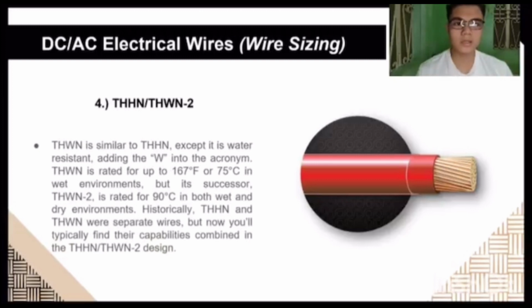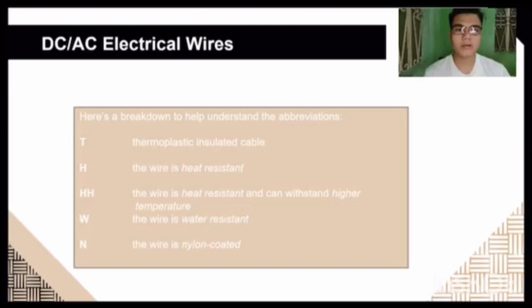Historically, THHN and THWN were separate wires, but now you typically find their capabilities combined in the THHN and THWN-2 design. So most wires in this category carry a dual rating and a mark approved for both applications. Here's a breakdown to help understand the abbreviations. T: thermoplastic insulated cable. H: the wire is heat resistant. Double H: the wire is heat resistant and can withstand higher temperature. W: the wire is water resistant. N: the wire is nylon coated.